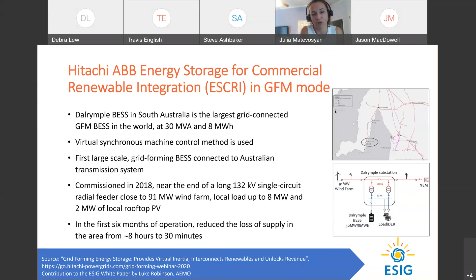They use virtual synchronous machine control method as in all other applications. The battery is 30 MVA, 8 megawatt hours. It is connected at the end of the long radial line that goes into Australian grid, 132 kV. It has 91 megawatt wind farm nearby, local load of up to 8 megawatt, and 2 megawatt of local rooftop PV. And so, as I mentioned, if the connection to the rest of the grid trips offline, the grid-forming battery can power up that island and therefore maintain reliability of supply to the island load. And so in the first 6 months of operation, it reduced loss of supply in this area from 8 hours to just 30 minutes. And we can go to the next slide, please.